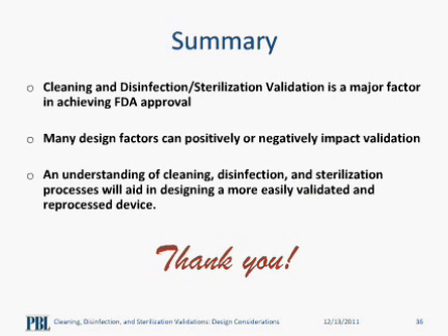In summary, cleaning and disinfection or sterilization validation is a major part of FDA approval. It is required to have a validated reprocessing instruction for reuse prior to release of the product in the market. However, for those products already out in the market, we're required to comply with the same requirement. Secondly, many design factors can positively or negatively impact validation. And lastly, understanding the effect of cleaning and disinfection or sterilization processes will help in designing a device that can be easily validated and reprocessed. So that's the end of our webinar, and we would like to open up for a question and answer session.